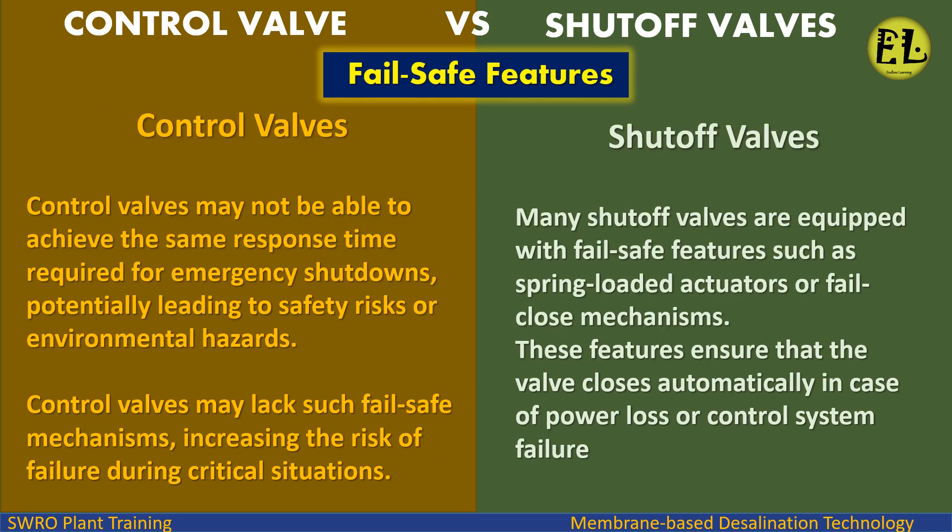Regarding failsafe features, control valves may not be able to achieve the response time required for emergency shutdowns, potentially leading to safety risks or environmental hazards. They may also lack failsafe mechanisms, increasing the risk of failure during critical situations. Many shutoff valves are equipped with failsafe features such as spring-loaded actuators or fail-close mechanisms, ensuring the valve closes automatically.